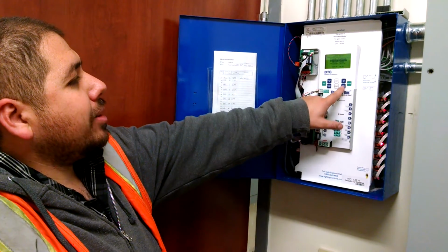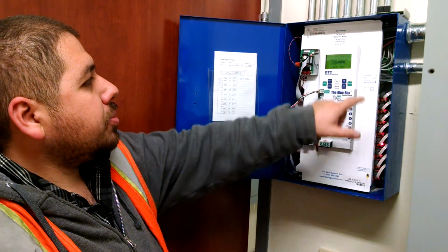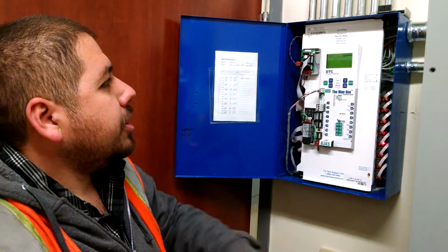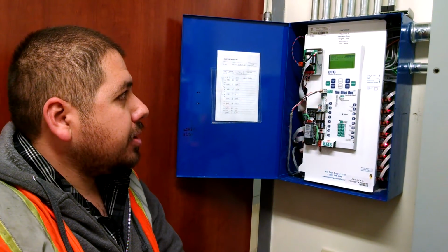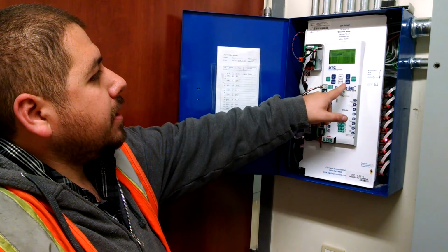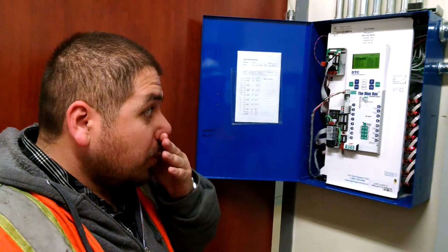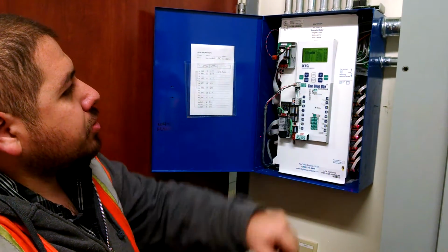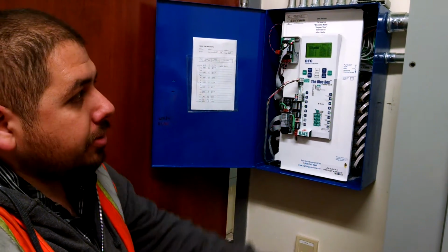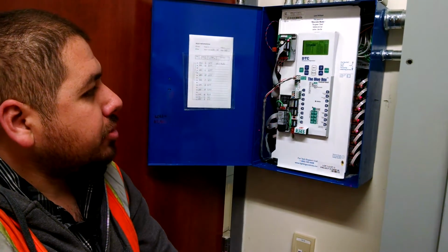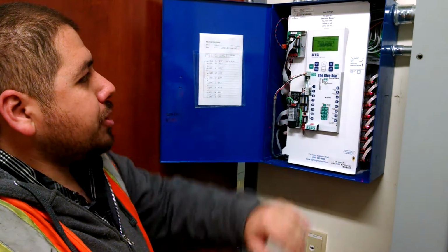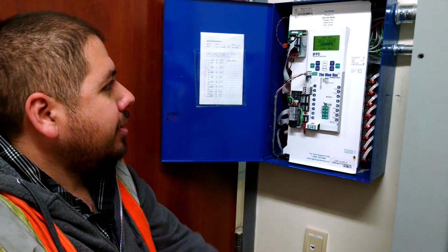Okay, another way to look at your groups, if you come down to group loads, press enter. There's group number 1, tab down, press enter, and there's the same screen, group number 1. Now here's a cool little trick. If you want to override group number 1 on, you can have group 1 highlighted, press scroll up, and it turns the entire group on. Scroll down, turns the entire group off. All right. You don't have any switches to program, so I'm not even going to talk about that.